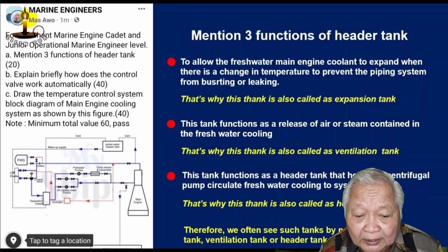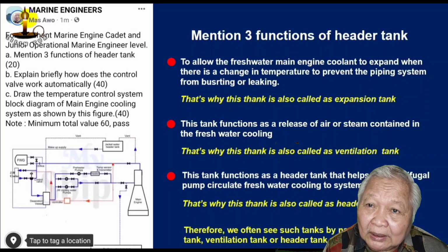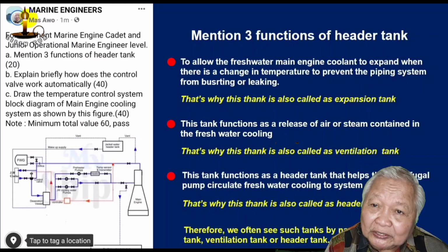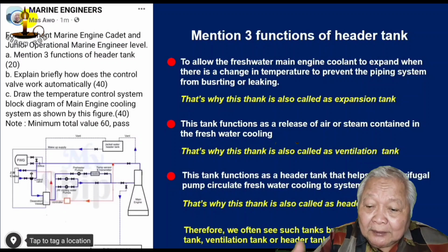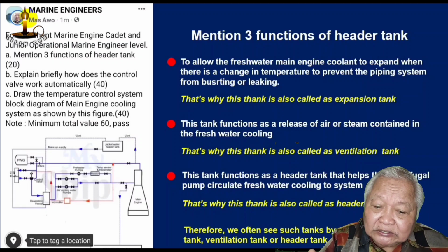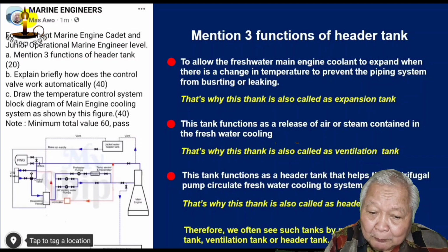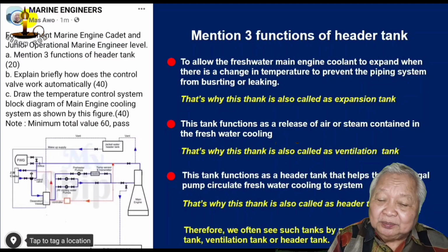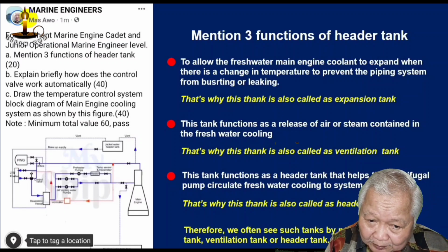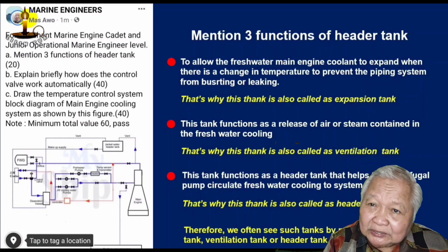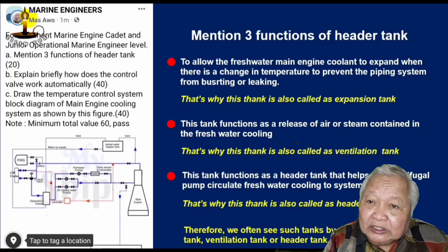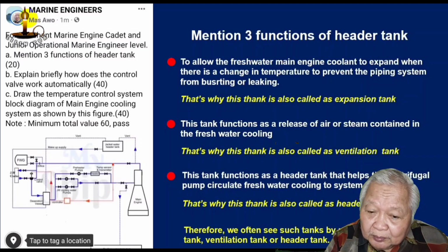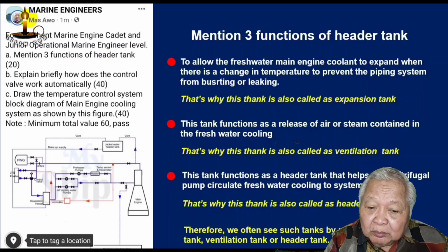The first function of the header tank is to allow the freshwater main engine coolant to expand when there is a change in temperature, to prevent the piping system from bursting or leaking.